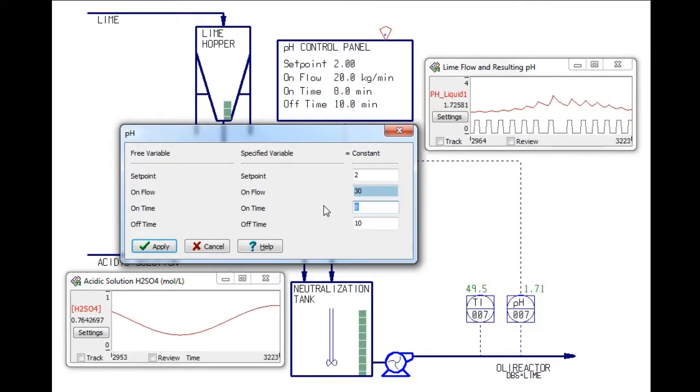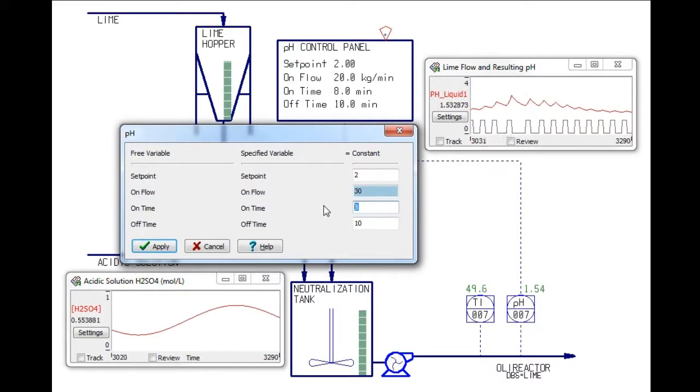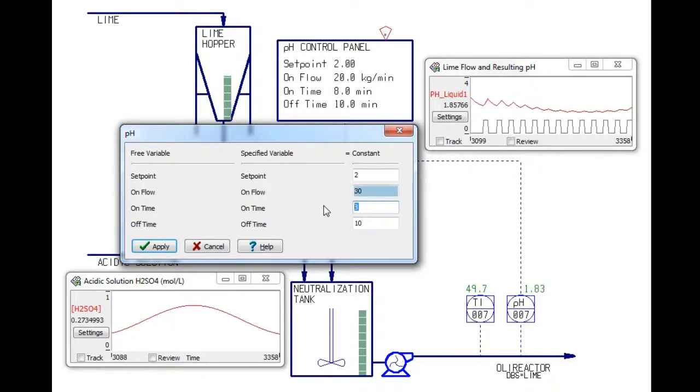With this higher feed rate, however, we may encounter the opposite problem of the pH going too high when the acid concentration is low. To counteract this, I will divide the on time and off time by half.